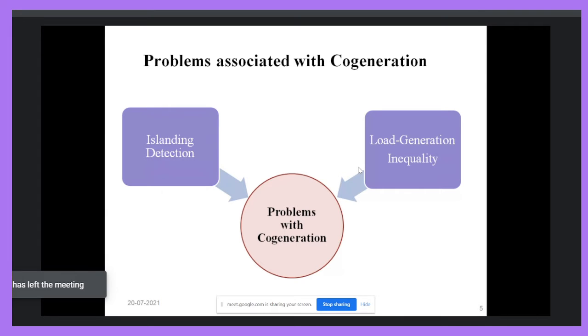Whenever there is a fault in the utility grid, definitely voltage will change and frequency will also change, because when a fault occurs there is a change in operating parameters. Suppose a short circuit occurs in the utility grid, due to that short circuit the voltage and frequency of the system will change. Voltage will reduce, frequency will also reduce, and current will increase. So we can sense voltage, frequency and current, and on the basis of the sensed parameters, we can decide that we have to separate our industrial system from the grid, and that process is called islanding. After islanding, you have separated your industrial plant from the utility grid.